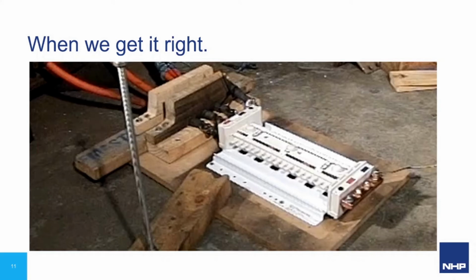So let's take for an example a bus bar chassis, although the same theory applies to any equipment that we select for our assembly. For this test, we will pass the rated prospective short circuit current through the chassis for a nominated time to arrive at a withstand rating.